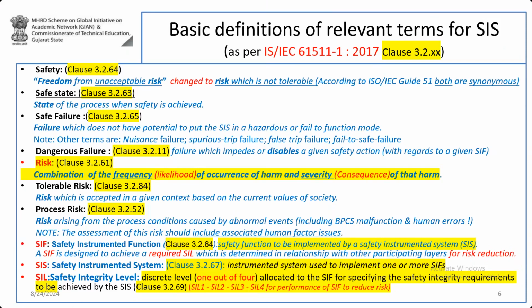The standard is in 3 parts. The first part is normative, which is mandatory. The second part is just explanation. So you have to read the first and second parts together: take the same clause number in the first part and look at the second part so that you will understand. It explains with examples. The third part is exclusively for SIL selection, which gives you the methodology of how to select the SIL by the risk graph method, risk matrix method, and the LOPA method. So this is how it is.